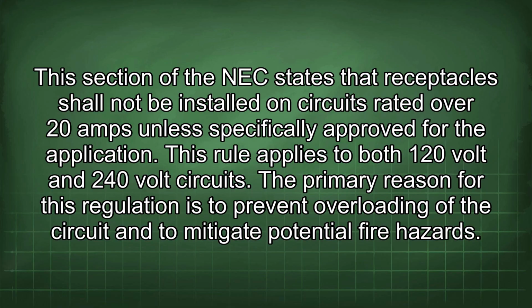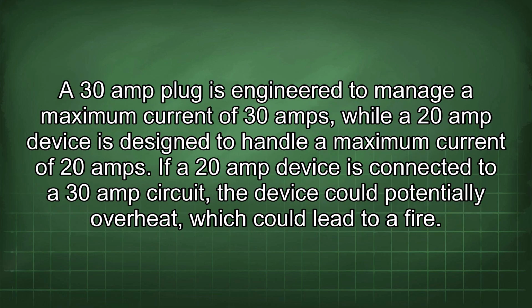The primary reason for this regulation is to prevent overloading of the circuit and to mitigate potential fire hazards. A 30-amp plug is engineered to manage a maximum current of 30 amps, while a 20-amp device is designed to handle a maximum current of 20 amps. If a 20-amp device is connected to a 30-amp circuit, the device could potentially overheat, which could lead to a fire.